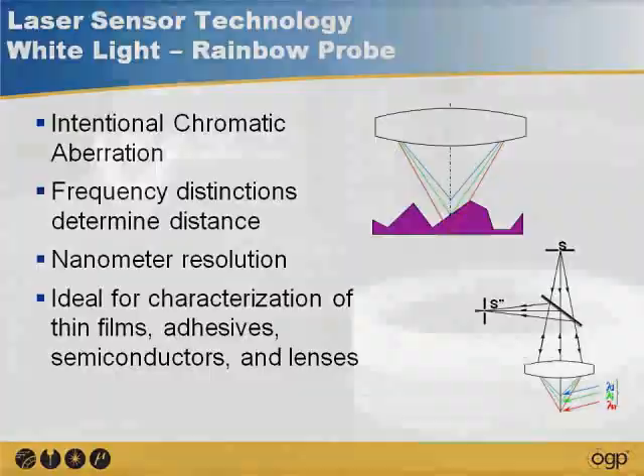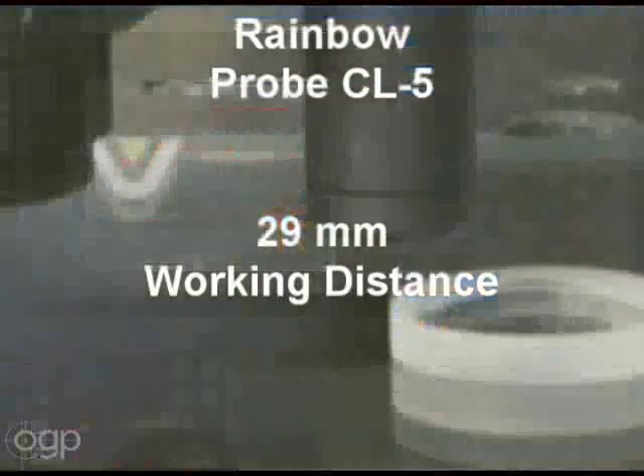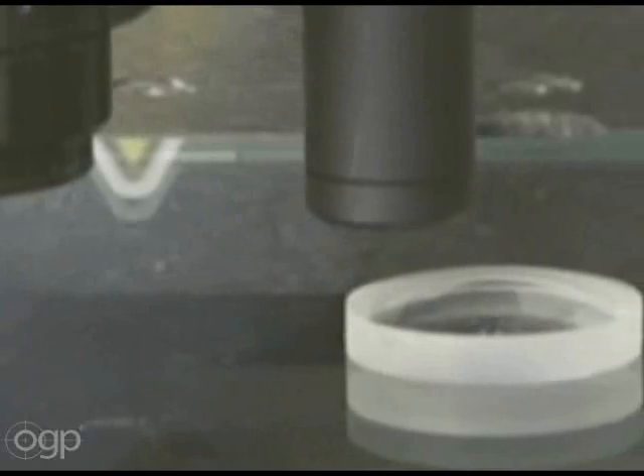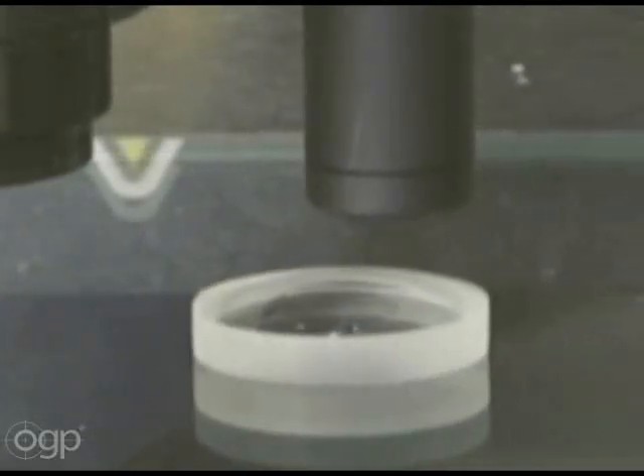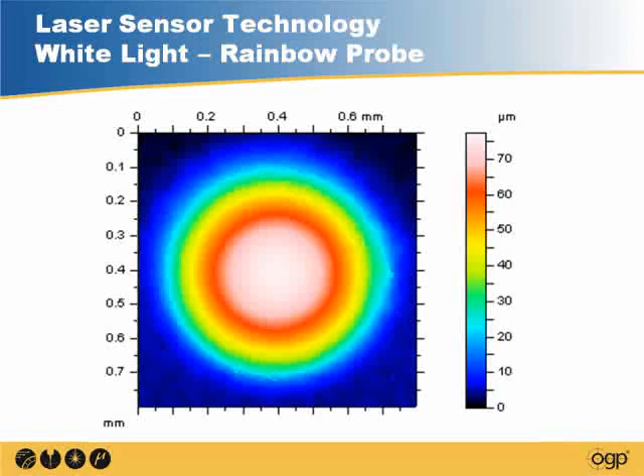Let's take a quick look at that one. This is called a rainbow probe that we use here. It's a white light sensor, so you don't see the actual spot on the surface, but it is scanning this lens. That black post there is actually the rainbow probe scanning over that surface and getting very high resolution on that aspheric lens surface. And then at the end of a three-dimensional scan on that, you might see something like this, where you're getting down to the color map of a surface and down into the micron level.